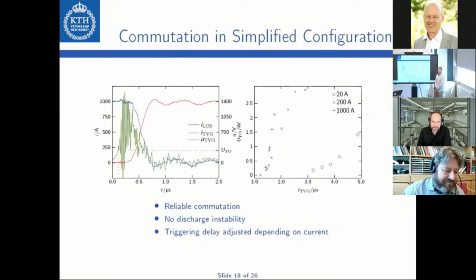Yes, so one would need to either measure the voltage of the snubber, maybe needing a bit more extra device for measurement, or implement a sort of lookup table where one stores these values. Depending on the current level, one says, okay, let's say the minimum voltage of the triggered vacuum gap is as shown 50 volts, but let's say we take 500 volts or 1 kilovolt to have some room. We can look at this table, choose this one, look at the voltage, and say for this current level we should have this delay. For this current level we have these curves; to get this voltage, we need this delay. That's the kind of implementation.